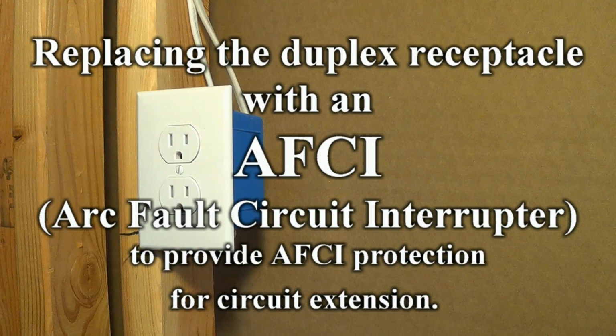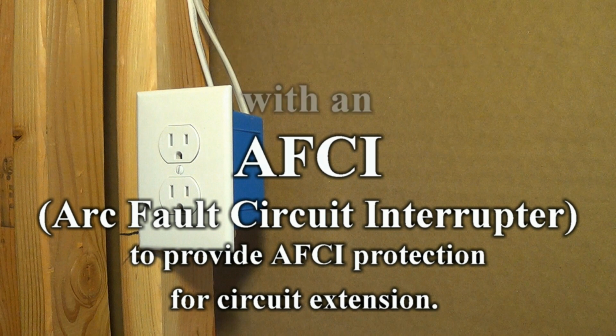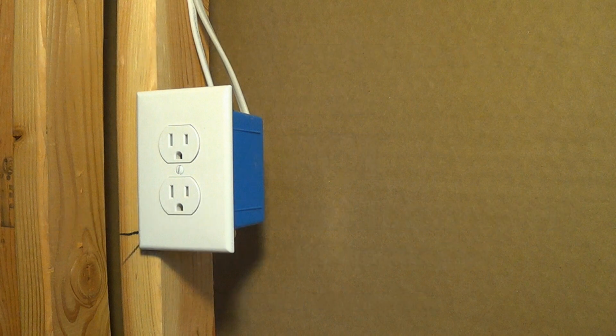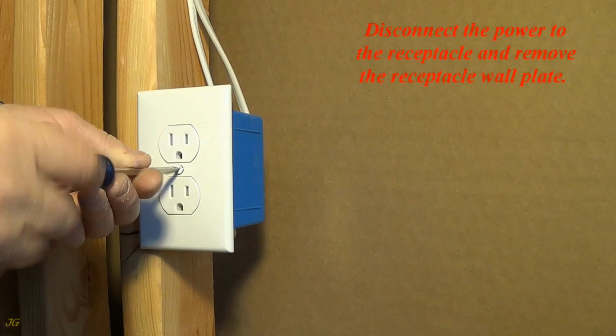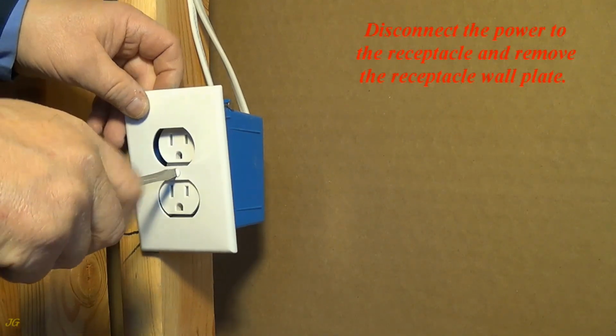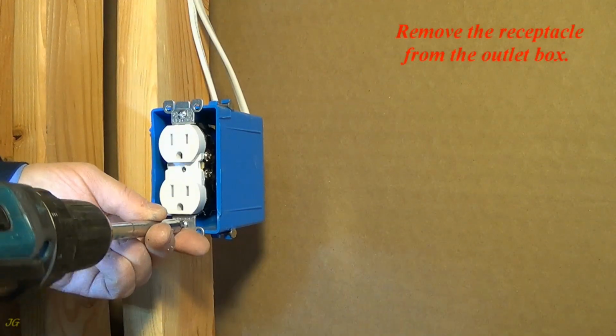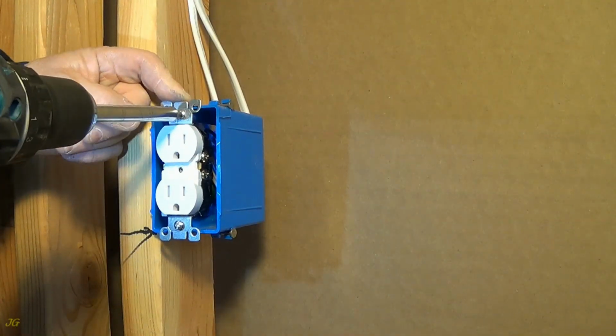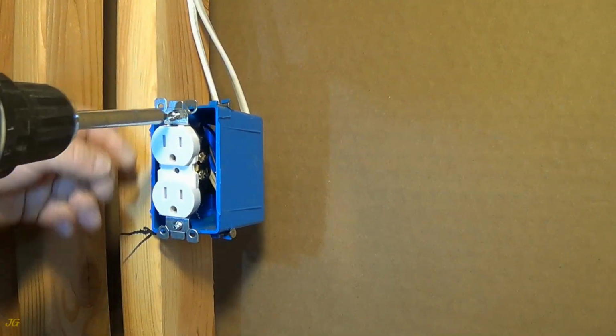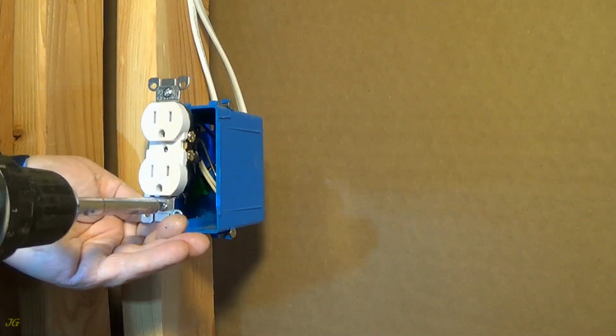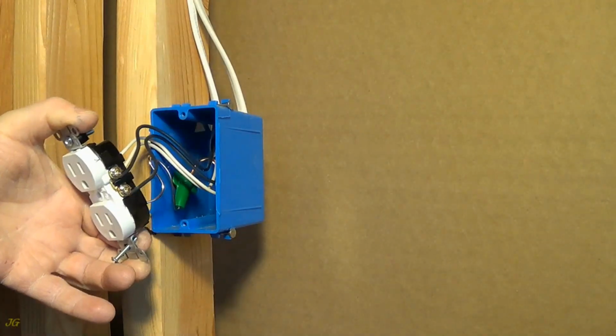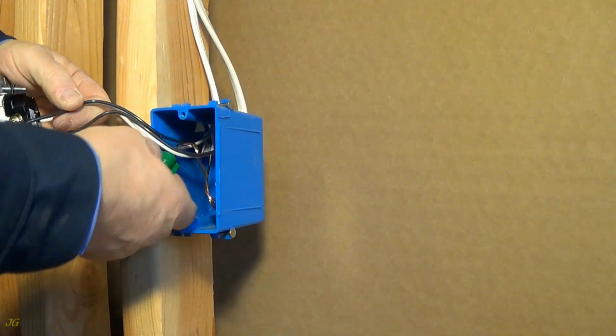Replacing the duplex receptacle with an AFCI, arc fault circuit interrupter, to provide AFCI protection for circuit extension. Disconnect the power to the receptacle and remove the receptacle wall plate. Remove the receptacle from the outlet box. Bring the cable from the new extended circuit.